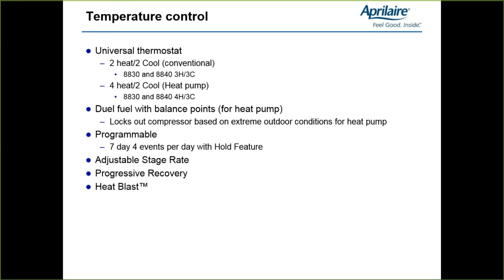Dual fuel with balance points. So in a heat pump application, the dual fuel will allow us to control the heat pump portion of the system, but then also shut off the heat pump when the gas-fired furnace is coming on. When we use an outdoor temperature sensor, we can actually enable the balance points, which will lock out the compressor when the temperature drops below these predetermined set points. These set points are determined based on the installer settings, so they can be changed. Typically, they're somewhere between 35 and 45 degrees, but it also depends on the type of refrigerant you're using, and so forth.